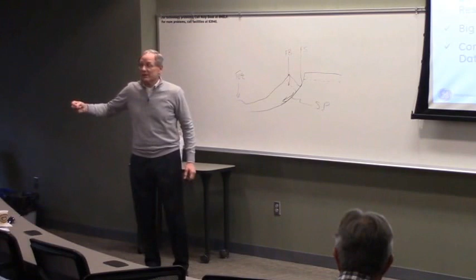We operate very siloed. The protection group buys a relay, puts it in the field, connects it to a circuit breaker, and their focus is on protecting the power system. But in that relay is the I2T information on the circuit breaker. When there's a fault, contacts open up to extinguish the arc. What's the magnitude of the current? How much time does it take for the arc to extinguish? The manufacturer of the breaker says when that breaker's experienced so much I2T, it needs to be maintained. And once the operations counter tracks how many times it's operated, that information's in the relay.